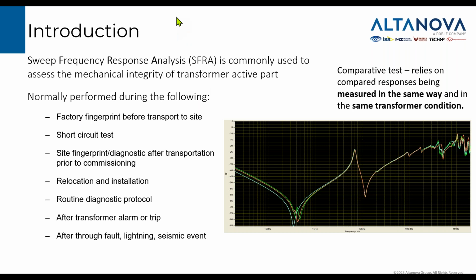So as a word of introduction, I will just briefly say what the sweep frequency response analysis, the so-called SFRA, is. This is a test technique in which we apply variable frequency voltage to the coils of the transformers, and we scan the coils while recording the response of the coil. Basically we do it for each winding, each phase of a transformer, and by doing that we obtain results like the ones presented in the graph on the screen.